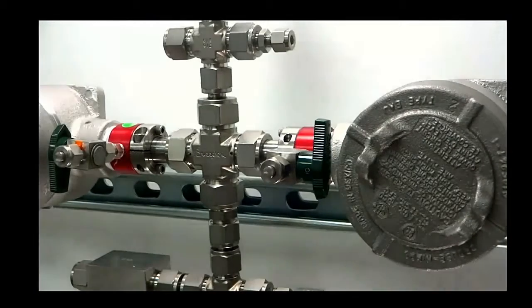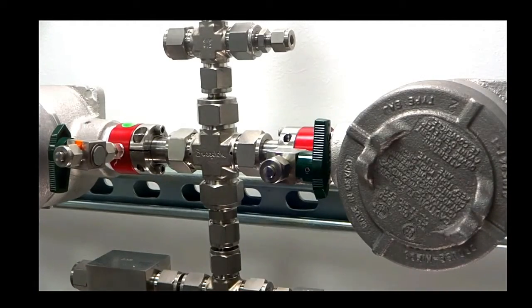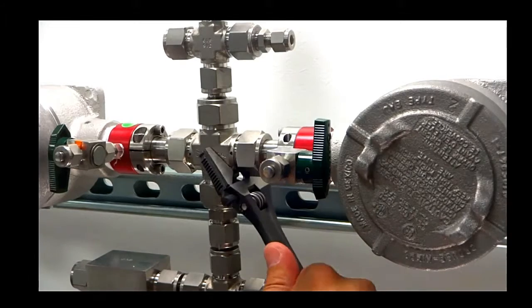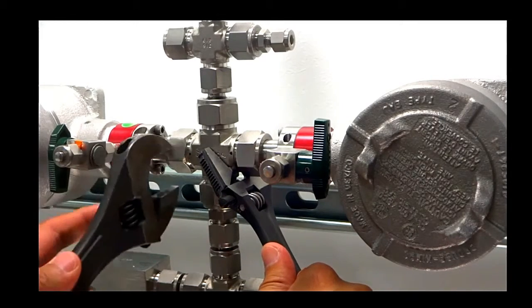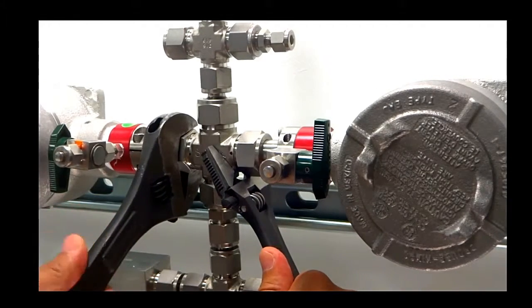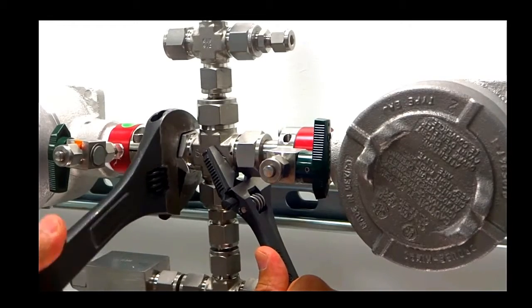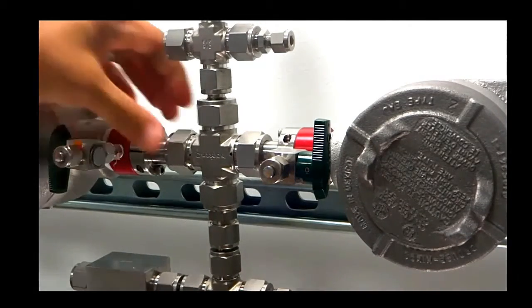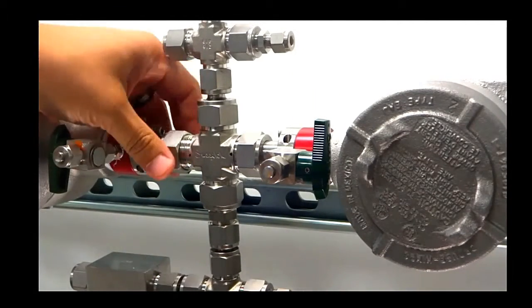Step 3. Loosen the nuts to access the probe lenses. These are standard Swagelok nuts. In order to prevent them from being stripped, we should support both sides before loosening the nut. Loosen the nut gently and then remove the rest of the way by hand.